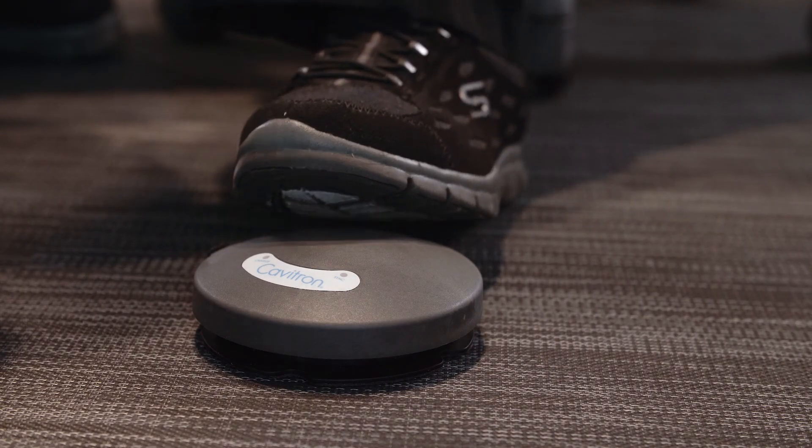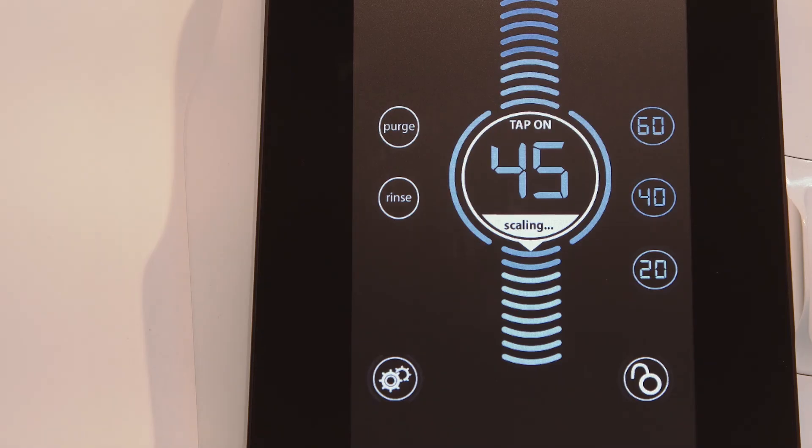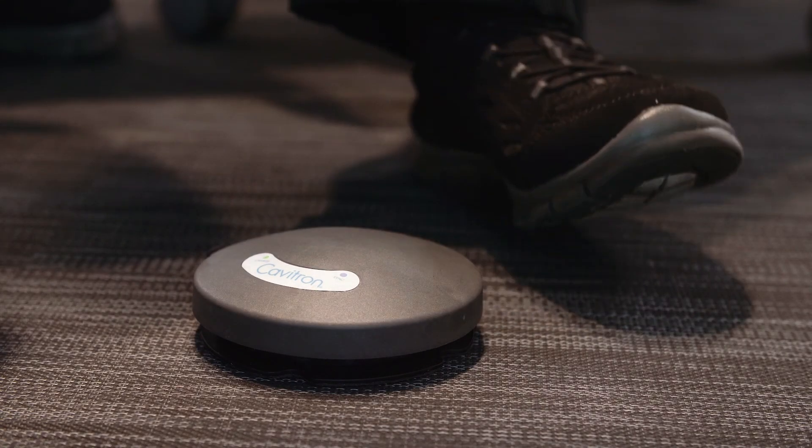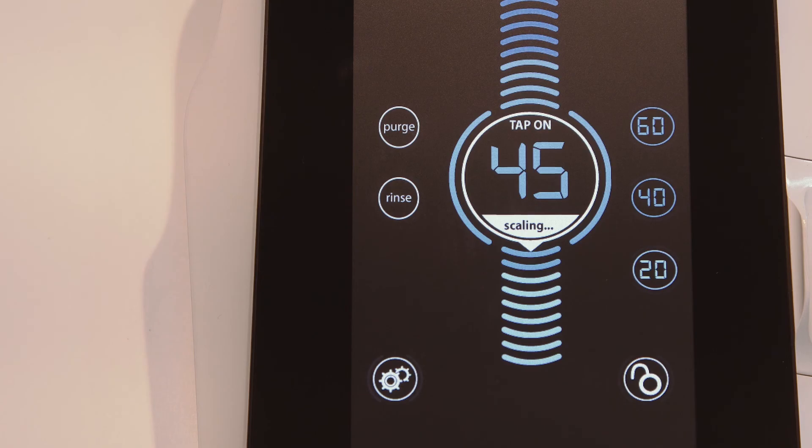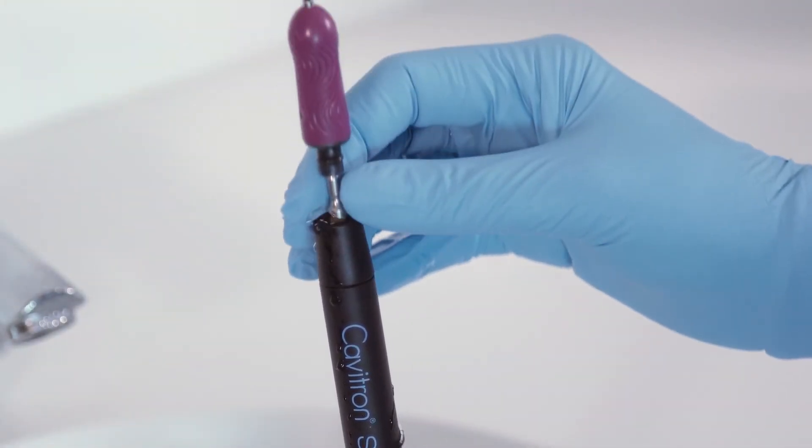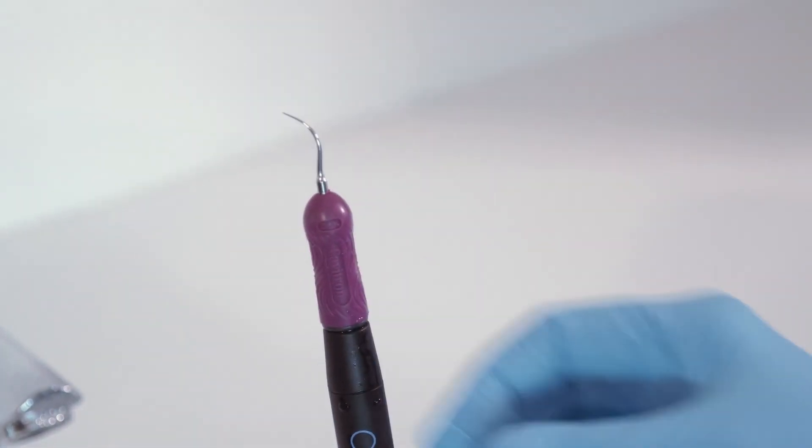With tap on technology activated, tapping on the foot pedal once will activate ultrasonic power for approximately four minutes. Tapping the foot pedal a second time will disable ultrasonic power and water flow. On the main scaling screen, a tap on indicator will appear in the power level display while scaling. Please note that tap on technology only operates when an insert is seated in the handpiece.